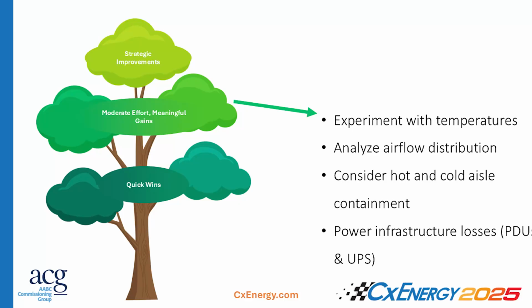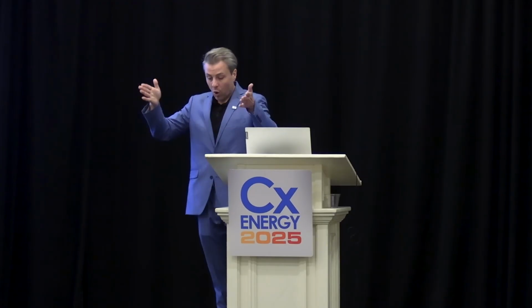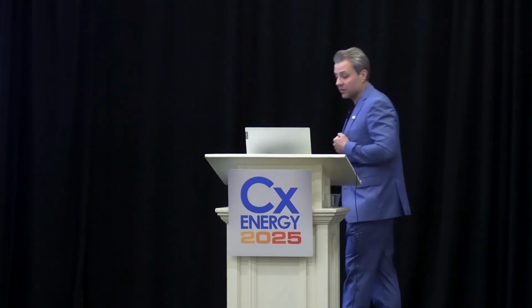So hot aisle and cold aisle containment is where you pump the air into a specific aisle, and then the servers are there. They pull the air from this aisle, shoot it into the other aisle, and then that is also contained. So they'll have walls that go all the way up, blank out panels, so there's no cross-contamination between the cold air and the hot air. So that's hot aisle and cold aisle containment. If you're in a data center from 1995, you probably don't have that, and it's not as expensive as you would think to implement it.